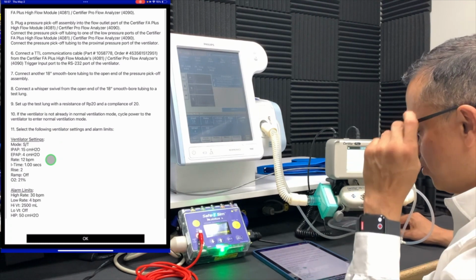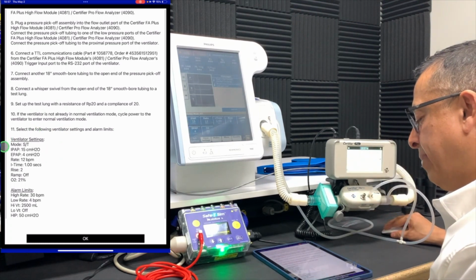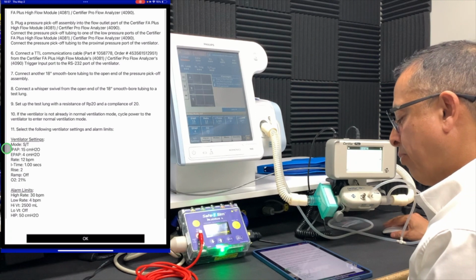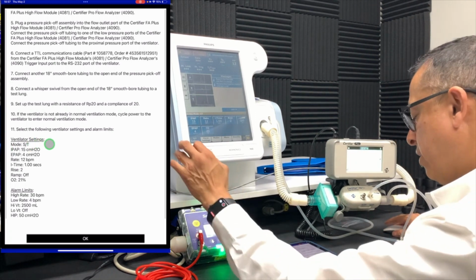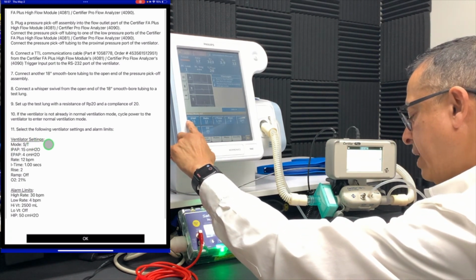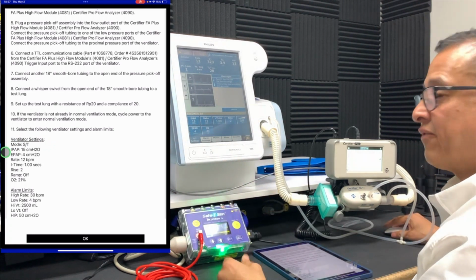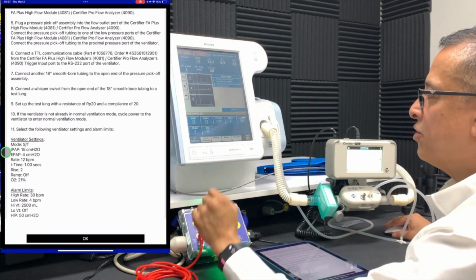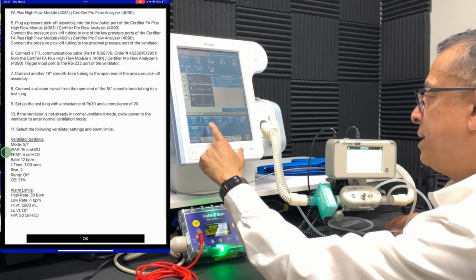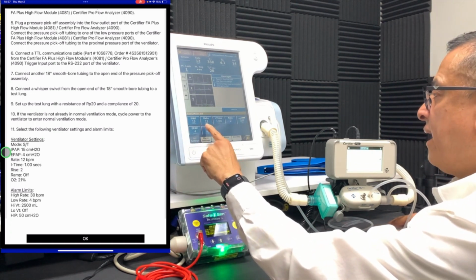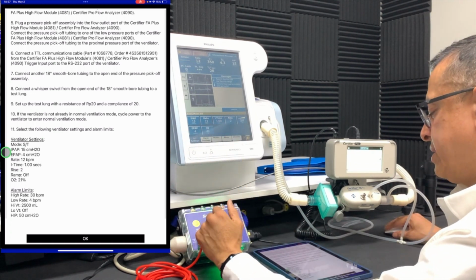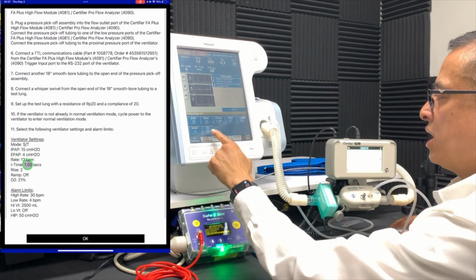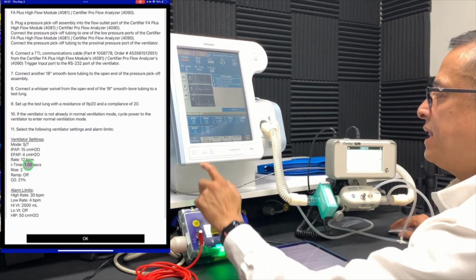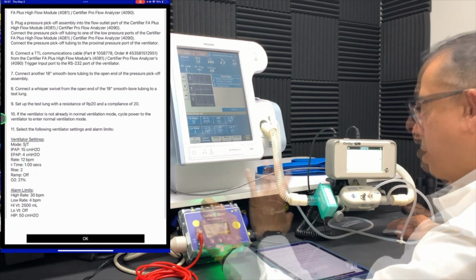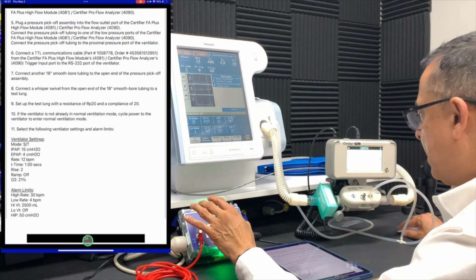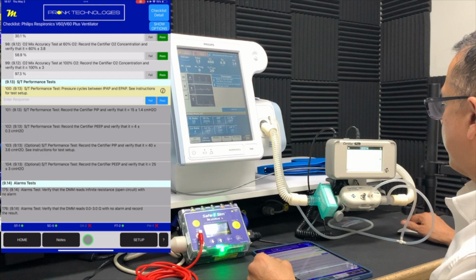So we're going to do some flow tests by basically setting the IPAP, the inspiratory positive airway pressure, to 15 centimeters of water, which is already set. The EPAP, or expiratory positive airway pressure, set to 4 centimeters of water. Our rate to 12 breaths per minute. The I time at 1 second, the rise time at 2, with an oxygen concentration of 21%. Then we want to set our alarm limits as well. We have it all configured properly. We've got our system set up properly here as well.